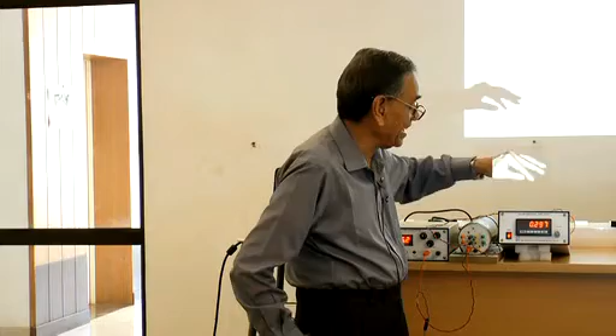The thermocouple 1 is connected, and thermocouple 2. The 2 leads of thermocouple 1 are connected to channel 1 and the 2 leads of thermocouple 2 are connected to channel 2. So if I put it in channel 1, it will measure thermo EMF of the thermocouple 1, and if I put it in channel 2, it will measure thermo EMF of the thermocouple 2.